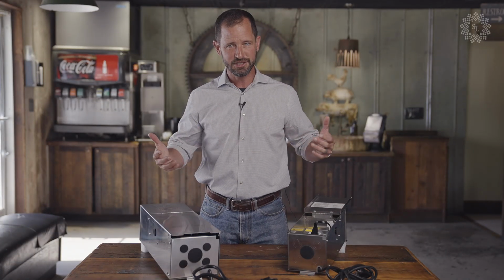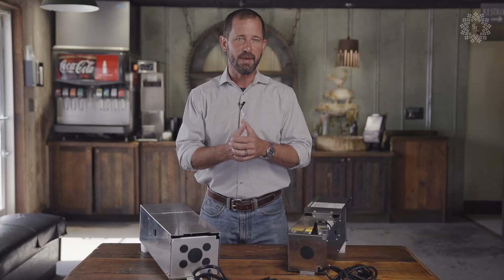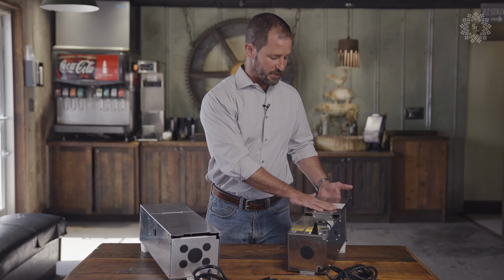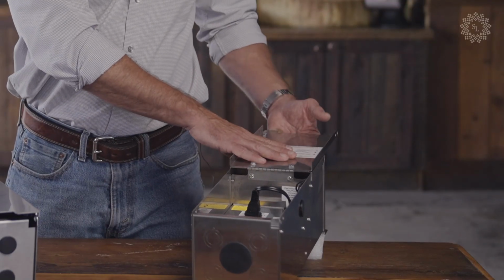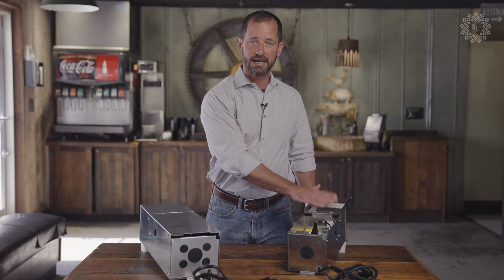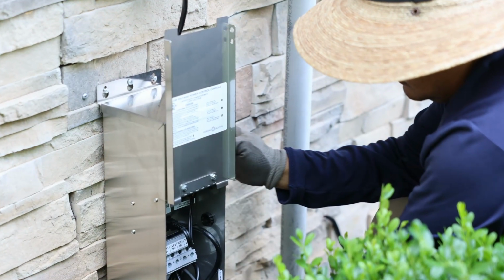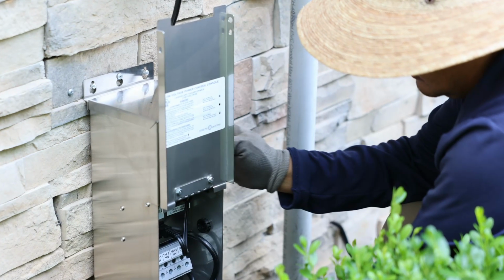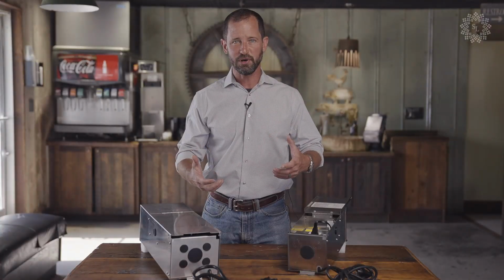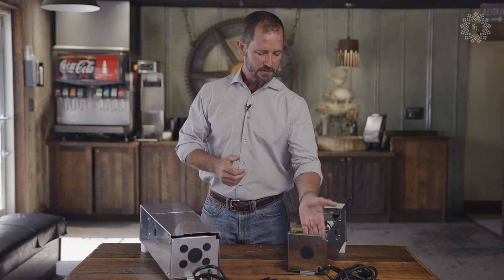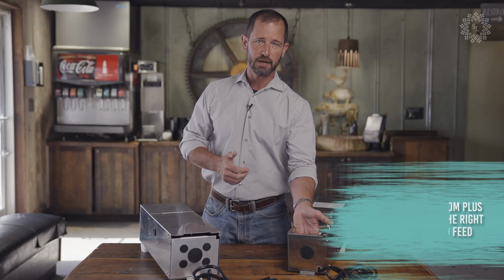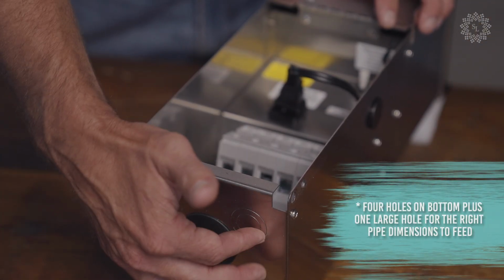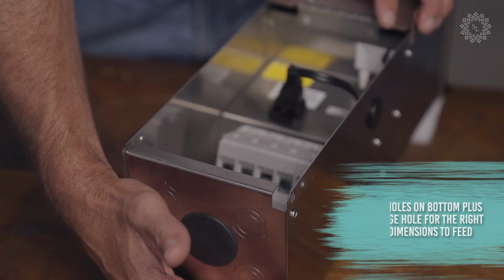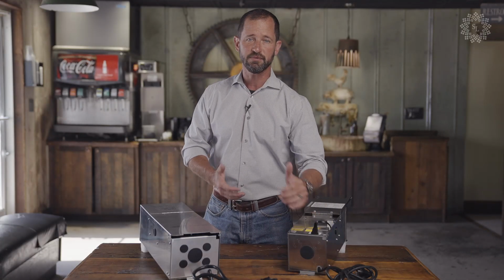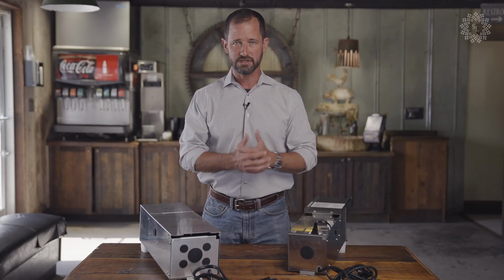Having done thousands of installations, we know what makes the install move faster and better. This door opens vertically and has a magnet on it, so as you're working on the transformer, it's easy to put the door up without taking it all apart. It has 4 different holes on the bottom and a large hole, so you can put a 1 inch to 1.25 inch PVC pipe into it, or smaller pipes, depending on how you're bringing the wires up into the transformer.